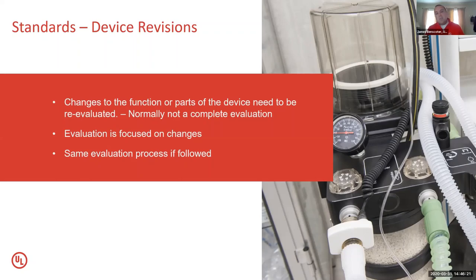The key here is the evaluation typically isn't always a full repeat of everything. It's really focused on what needs to be evaluated based on the specific part and change. So if I'm changing a pump on, let's say, a hemodialysis unit, I know that there are very specific requirements with regards to testing that will need to be repeated. So within every situation, it needs to be reviewed.